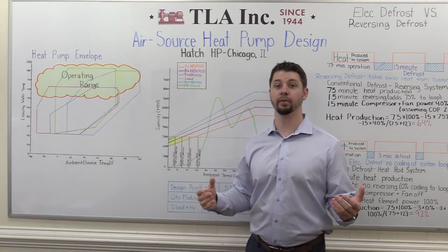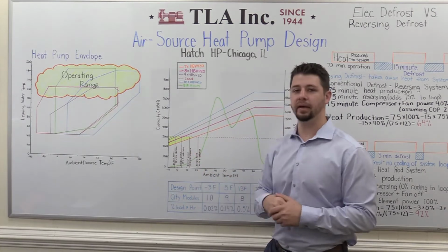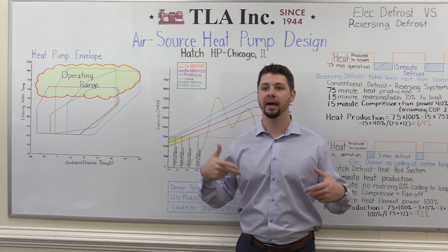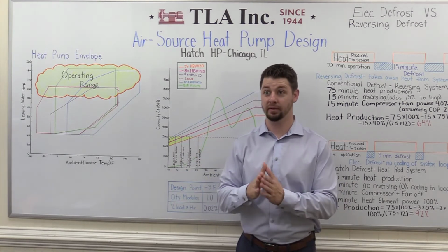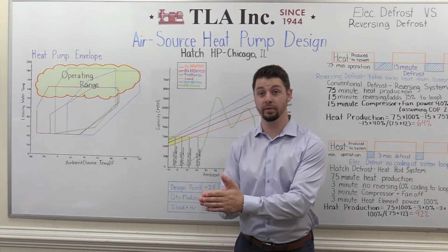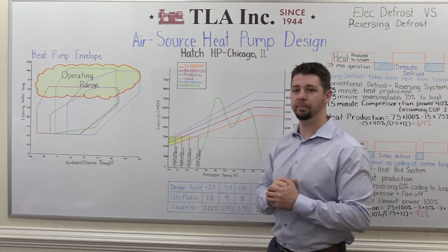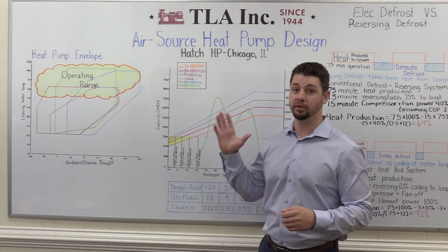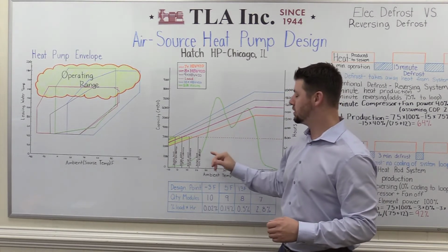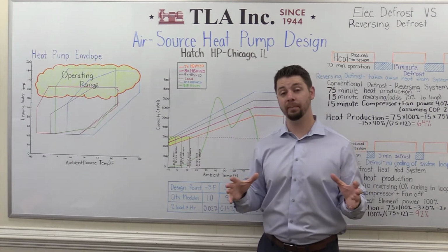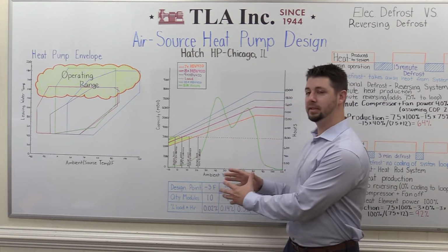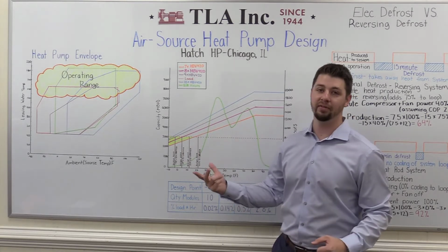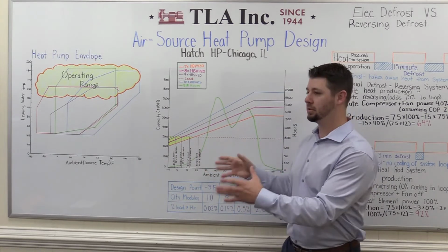And you say, well, Tyler, what are we doing at peak demand? Well, we put a tank inside with a straight electric as supplemental MBH, in the form of kW, to boost up this temperature. You could also put the heater inside the unit, like we do on the Transom Hatch units.